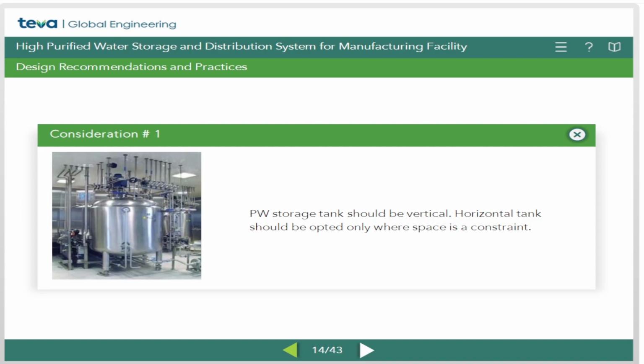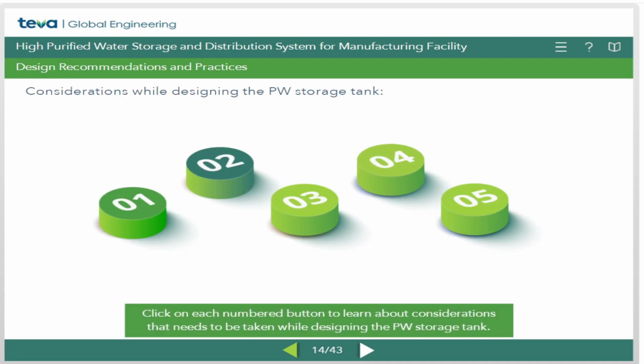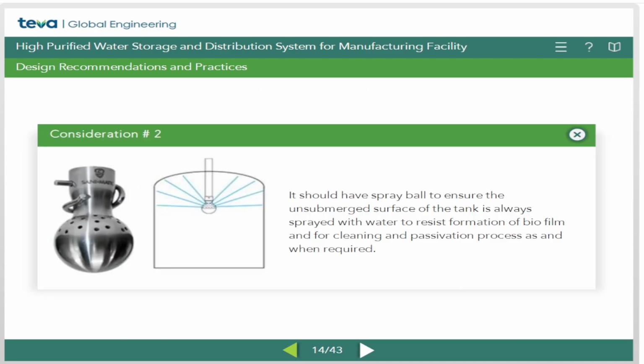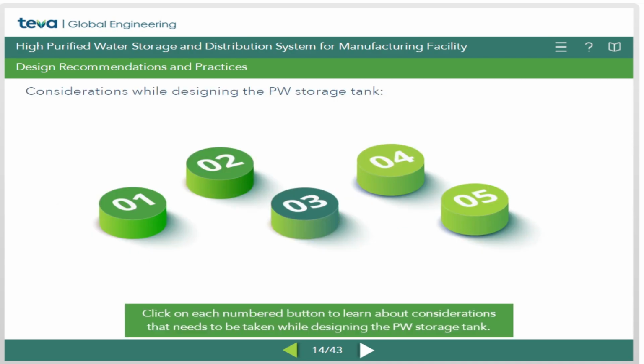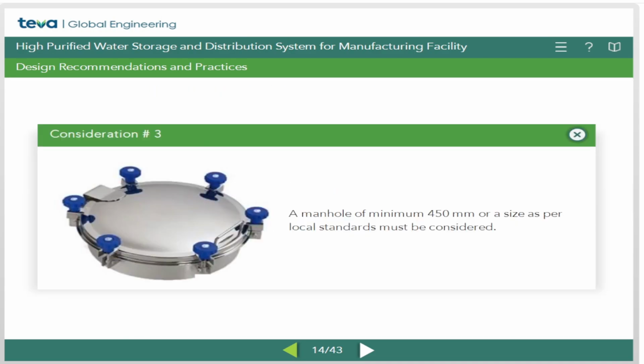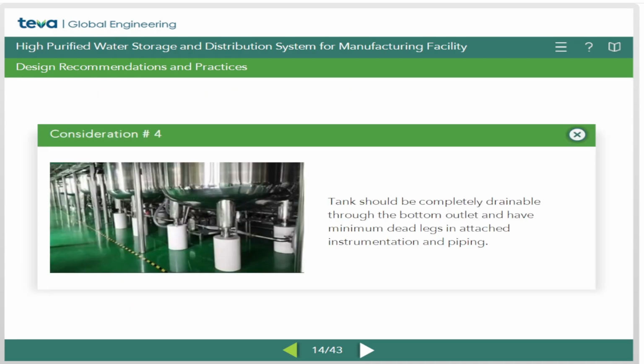Purified water storage tank should be vertical. Horizontal tank should be opted only where space is a constraint. It should have spray ball to ensure the unsubmerged surface of the tank is always sprayed with water to resist formation of biofilm and for cleaning and passivation process as and when required. A manhole of minimum 450 millimeters or a size as per local standards must be considered. Tank should be completely drainable through the bottom outlet and have minimum dead legs in attached instrumentation and piping.